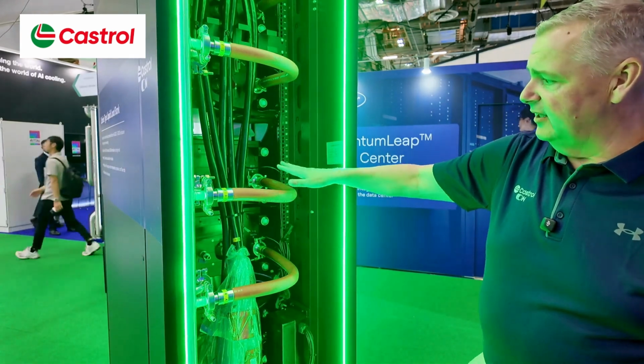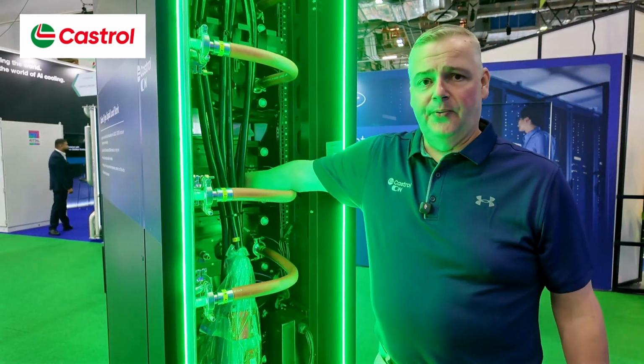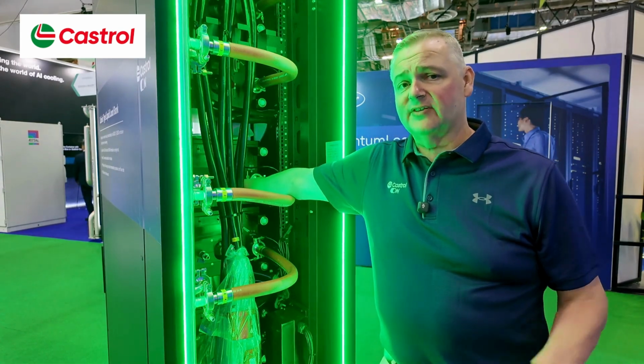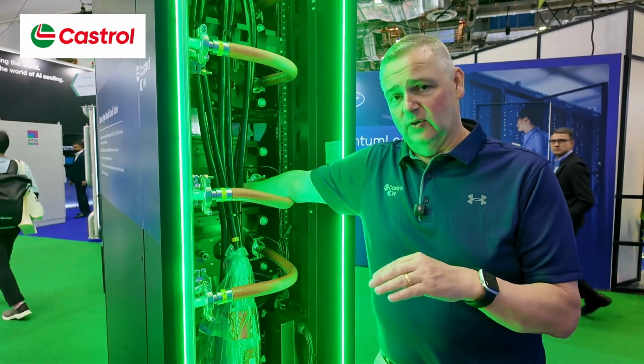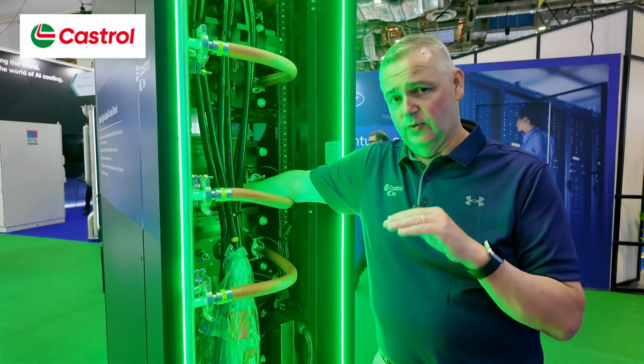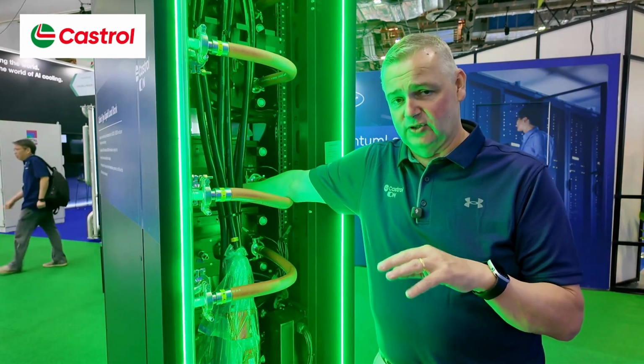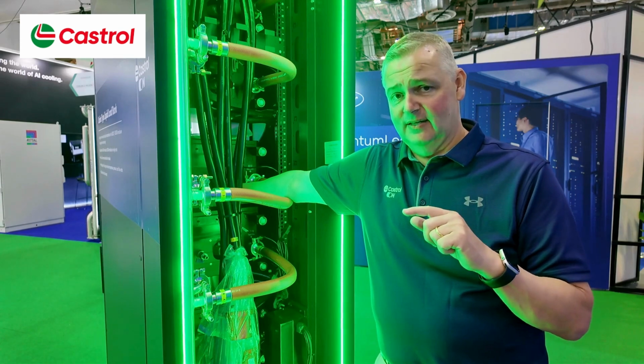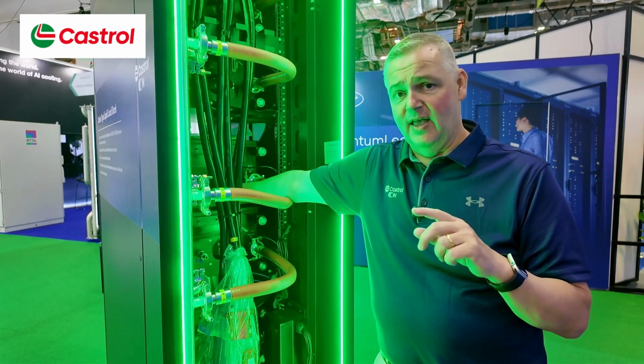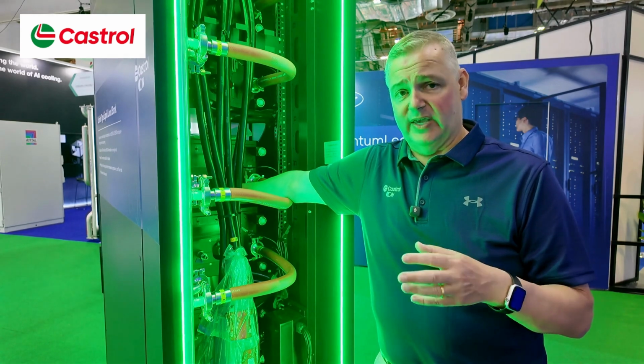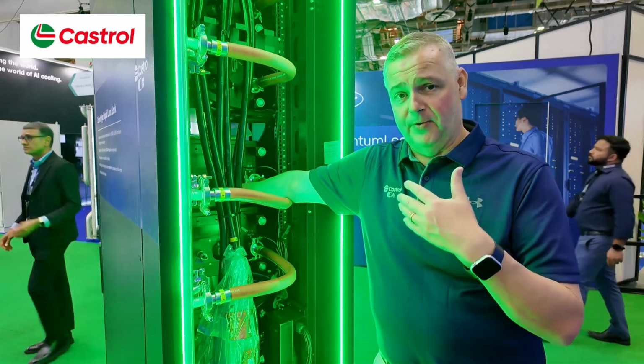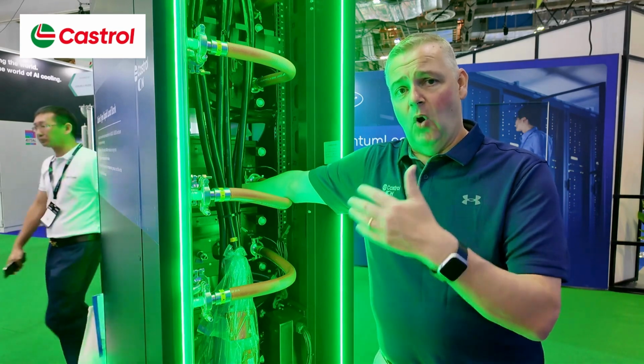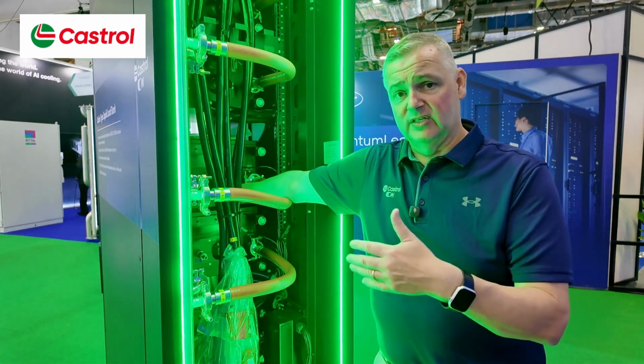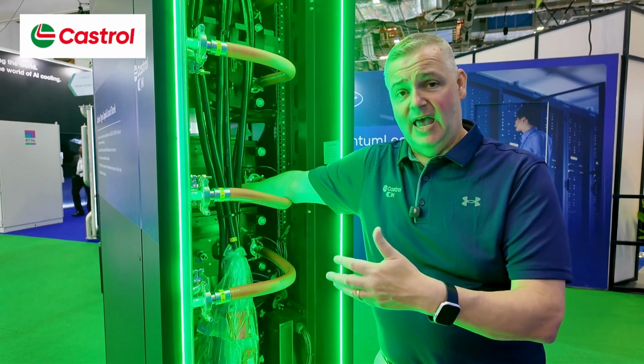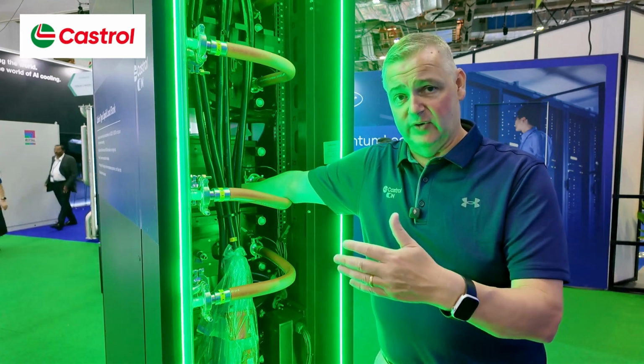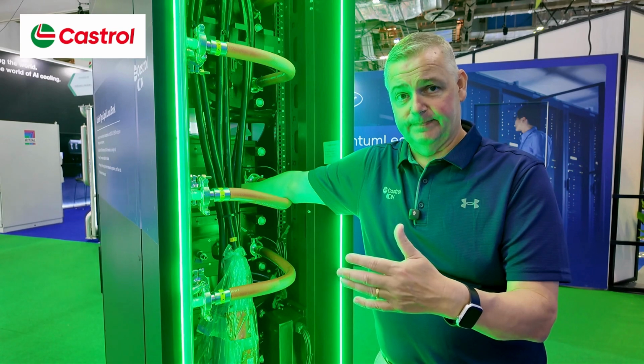There's not too much else at the back apart from a pressure valve, and that's very important because that can set the pressure that we should be seeing at an individual server level, and it can also help us to create fault scenarios. In that way, we can test if we set the pressure too high, what happens in terms of warnings and alarms in the BMS, and make sure that everything in that secondary fluid network is working as it should.